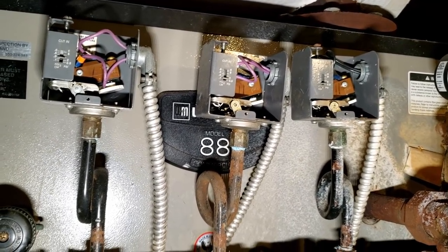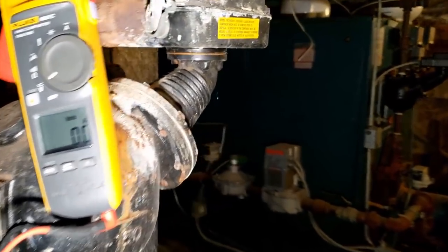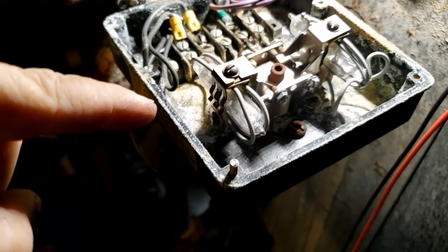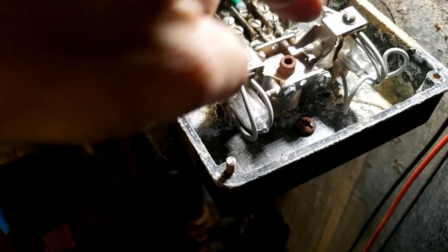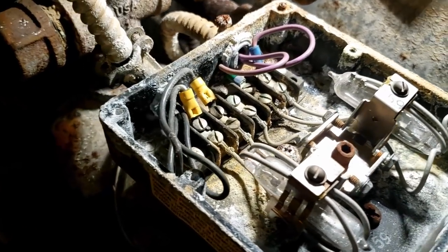So now we're going to work our way over to the floats. The one right here is our high voltage going to our pump. That right there is high voltage going to the control, so there's no issues there with that. It's closed. The only one left here is this one. This really is about the only things that shut this thing down other than that end switch down there on bottom.